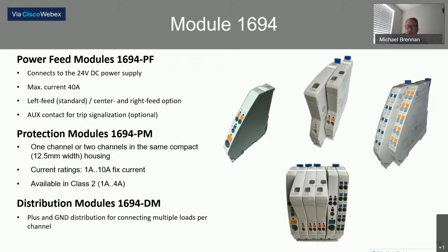So I'm reducing the overall number of terminals that I'm using, and I'm also additionally making it easier to distribute 24 volts. I'm going to have diagnostics. I'm going to know when I've reached 90% of my circuit load. I'm going to know if there's an individual fault, and I'm going to be able to easily and quickly turn off individual circuits if I need to do any sort of testing.